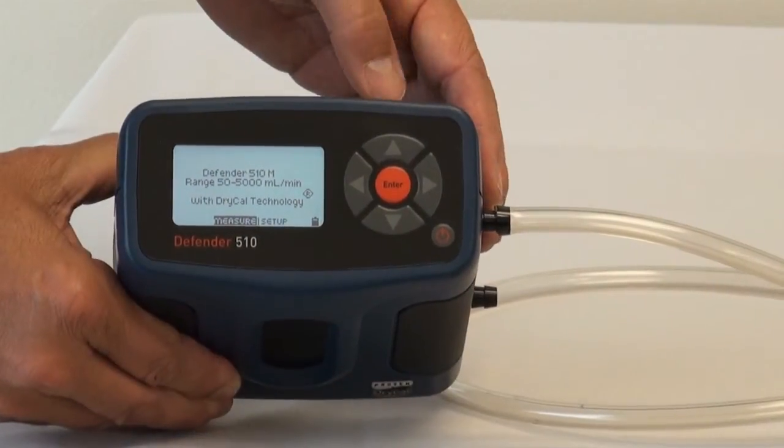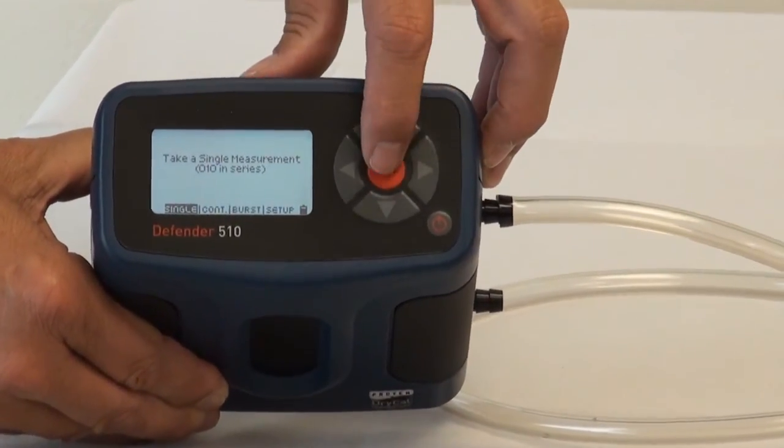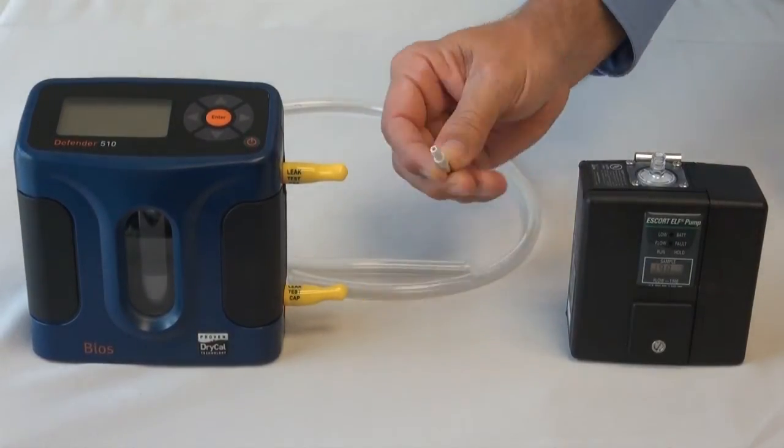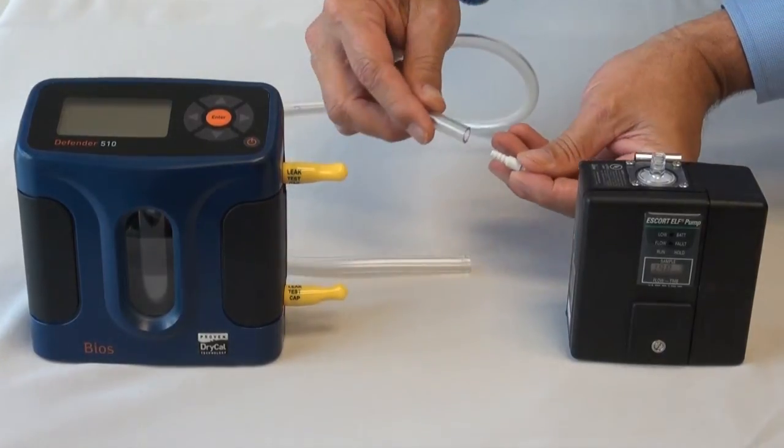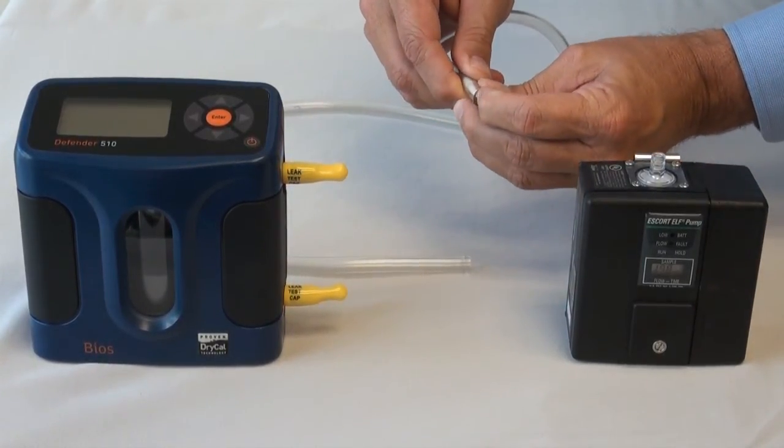If you are using a BIOS DryCal or BIOS Defender as your primary calibrator, it is necessary to use the isolating flow restrictor. This restrictor is provided with each new Escort Elf pump or can be purchased separately.